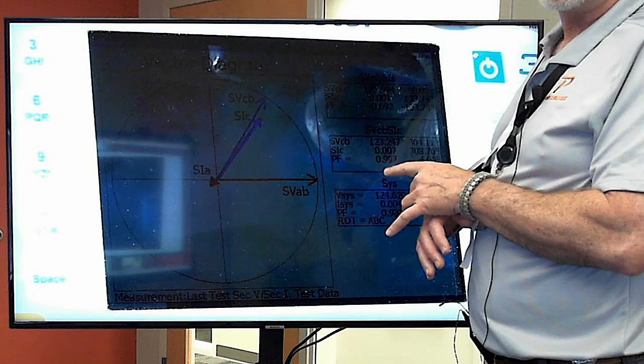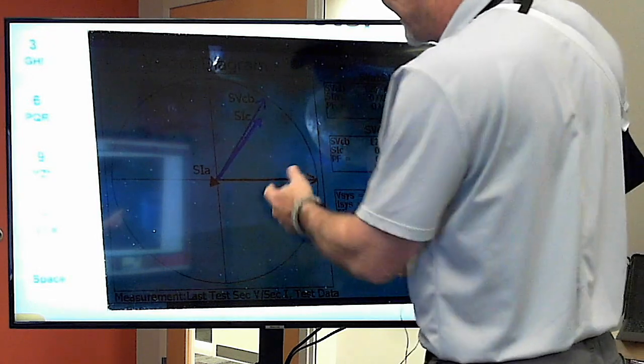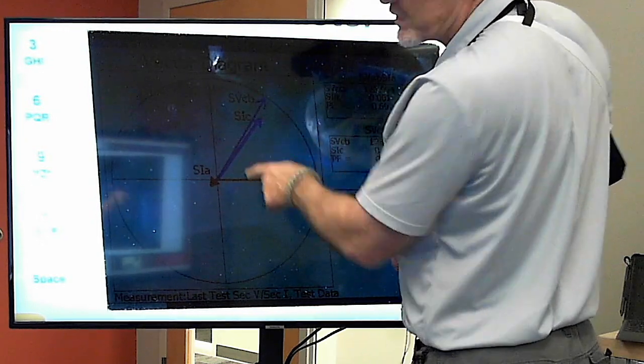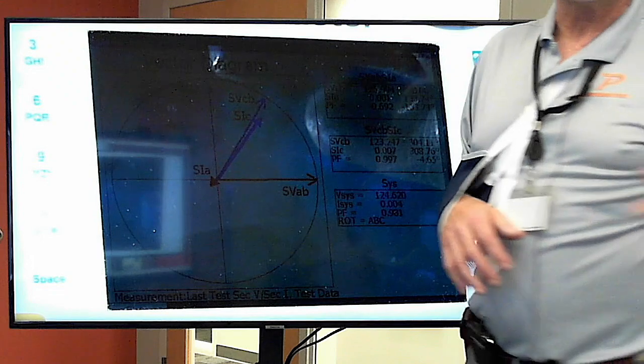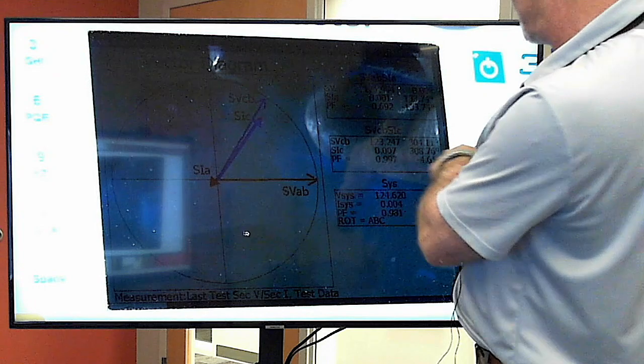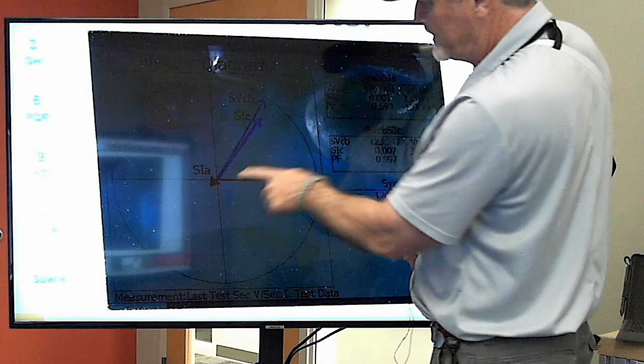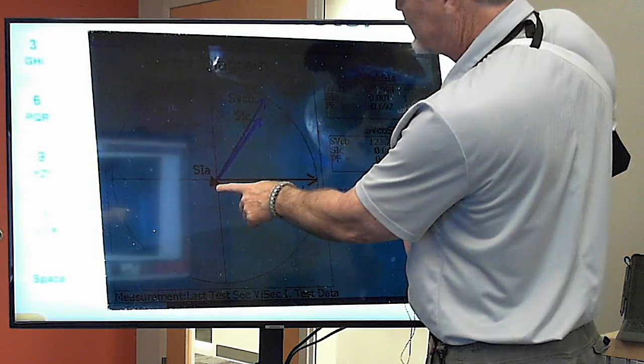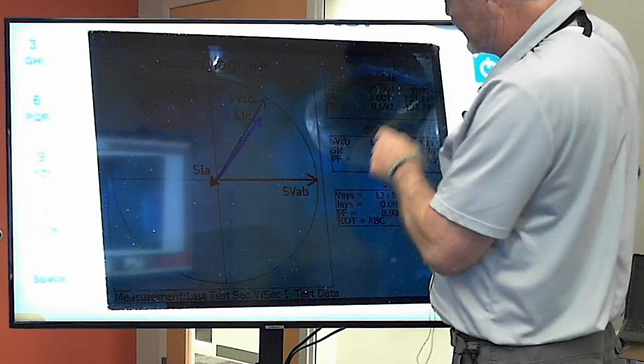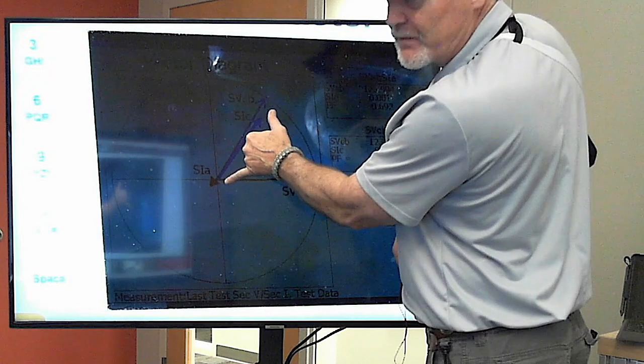But what's interesting about this is, if you look at it, you would initially look at this and go, wait a minute, I thought you said there wasn't any load on there. But what the thing is, it looks at this, and it's almost like an auto ranging. What happens is it looks at the lowest one here, which was 0.007, and then it's got 0.001. So it's got only 0.001 of secondary current here on A phase. Well, then it's going to scale off that, and that's the 0.007. So no, it still doesn't have any load. You need to look at the numbers over here. You can't be fooled by the vectors sometimes, because they're going to auto scale against one another, okay?